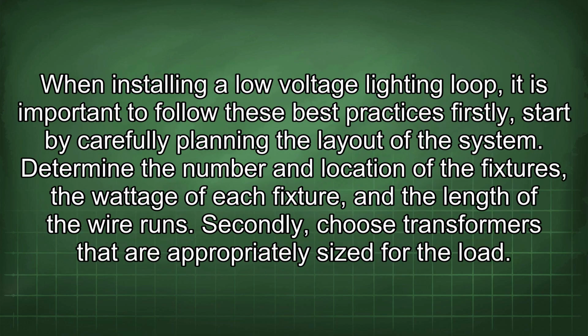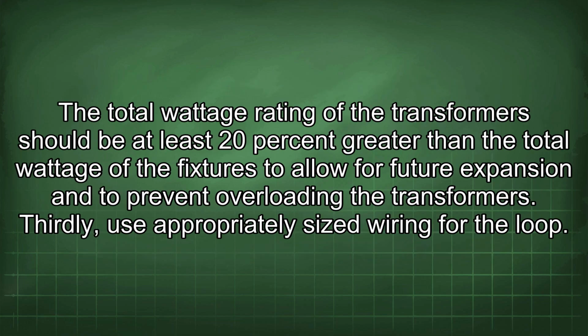When installing a low-voltage lighting loop, it is important to follow these best practices. Firstly, start by carefully planning the layout of the system. Determine the number and location of the fixtures, the wattage of each fixture, and the length of the wire runs. Secondly, choose transformers that are appropriately sized for the load. The total wattage rating of the transformers should be at least 20% greater than the total wattage of the fixtures to allow for future expansion and to prevent overloading the transformers.